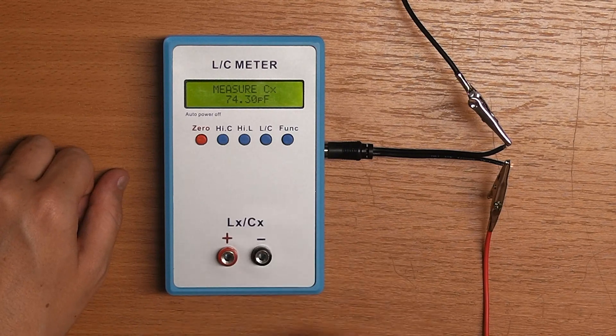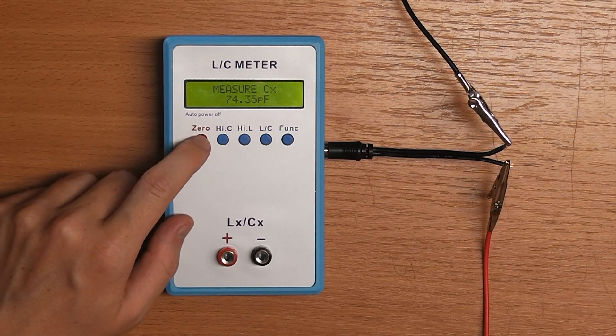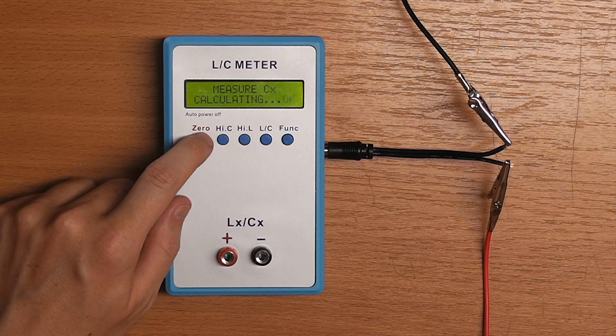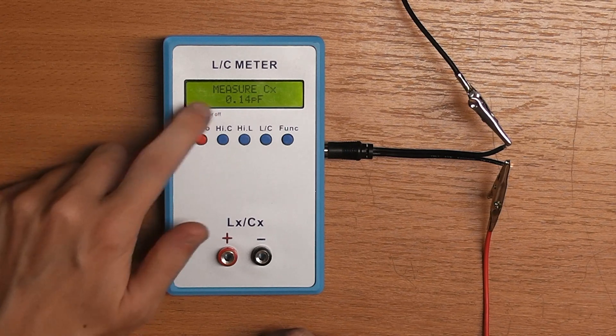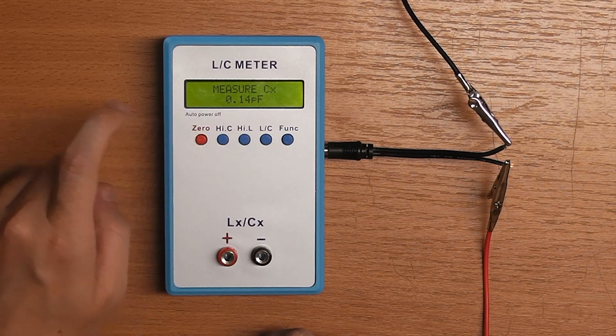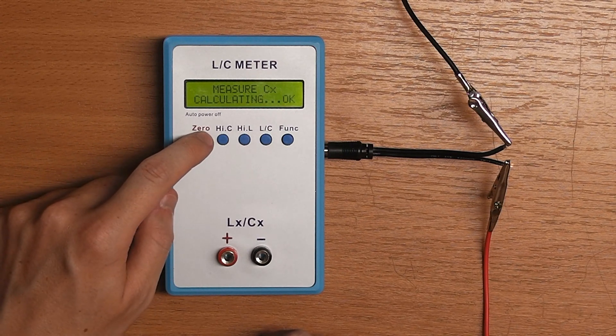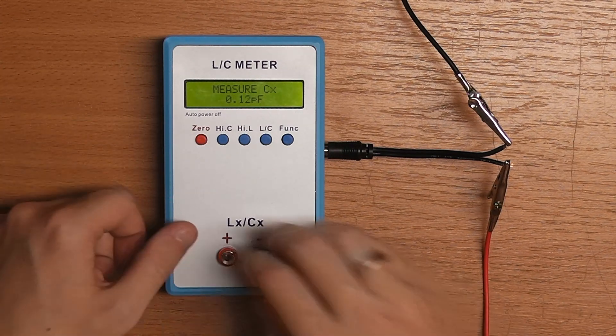You see that it currently has an error of about 74 pF. If I press this zero button, it will say calculating and if it says OK and I release it, it will have zeroed out the error. So currently it's at 0.15 pF error. Usually you do that after you connect your leads and everything to cancel out the measurement error that is caused by the leads.